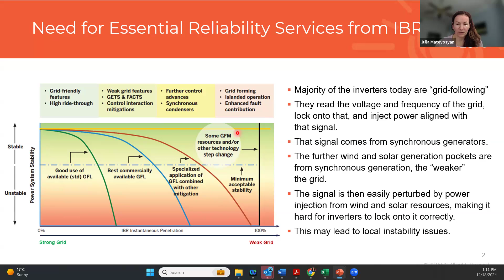All right, so what are the issues? I kind of touched on that in the previous slide. But as synchronous generators are going away and being displaced by inverter-based resources like solar, storage, wind, synchronous machines are becoming scarce, and we need to lean more and more on inverter-based resources for provision of services. The issues that the grid can encounter are related to frequency stability. So this is related to low inertia, leading to a fast rate of change of frequency after generation contingencies or load contingencies. So large generator trips and the frequency decline is too fast, where you cannot arrest frequency in time, and it may lead to under frequency load shedding or just instabilities on the grid.